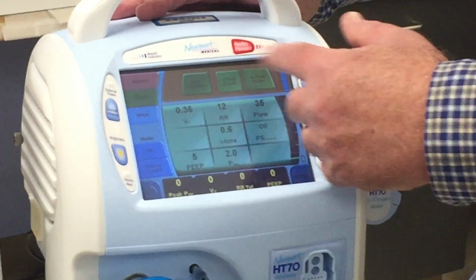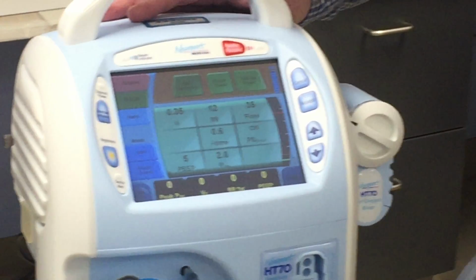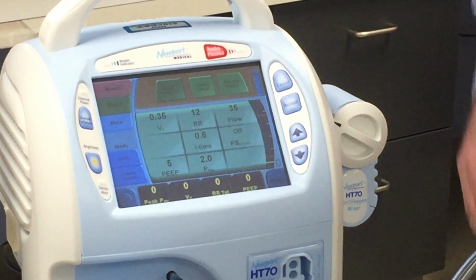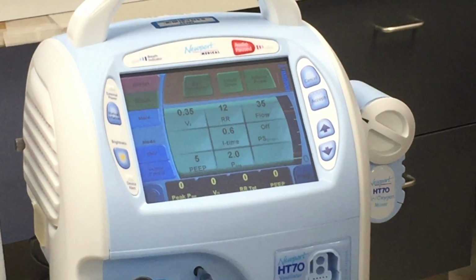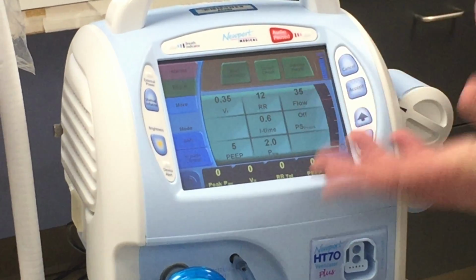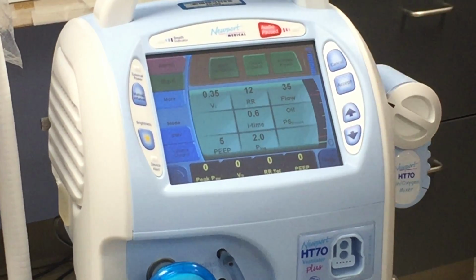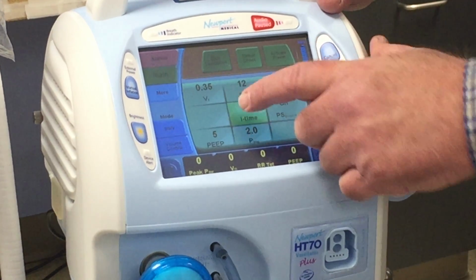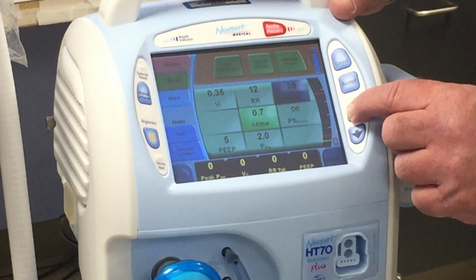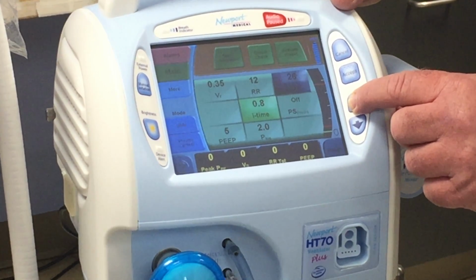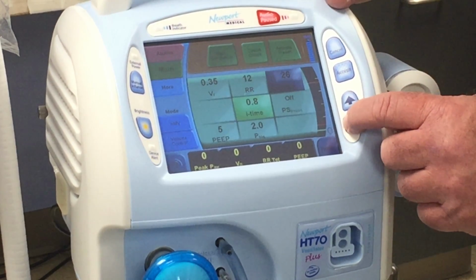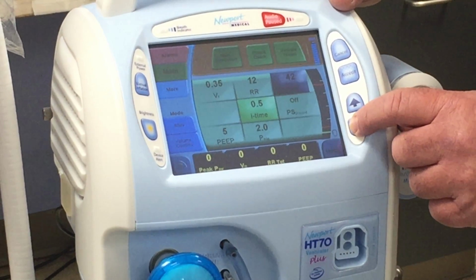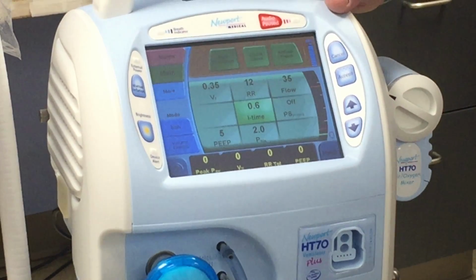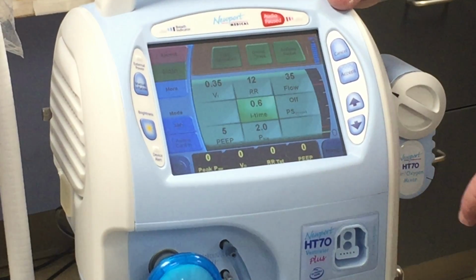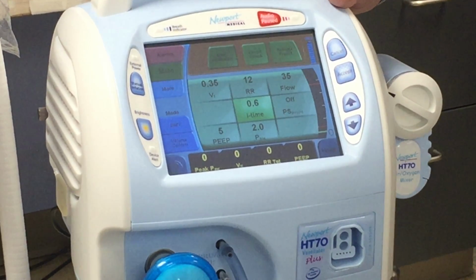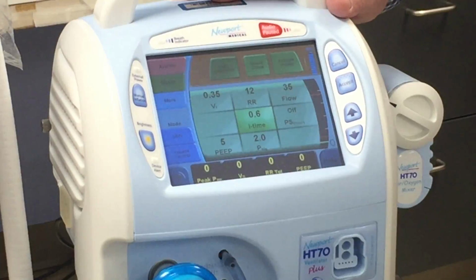Okay. So again, this is our main screen. We have our patient set up at 350, rate of 12. We can adjust our flow. Our flow and I-time work together. If I increase my I-time, you can see how it affects my peak flow. If I lower it, it increases my peak flow. Those two are interconnected. I have PEEP of 5, and I have a trigger of 2.0, and that's -2 centimeters of water pressure.